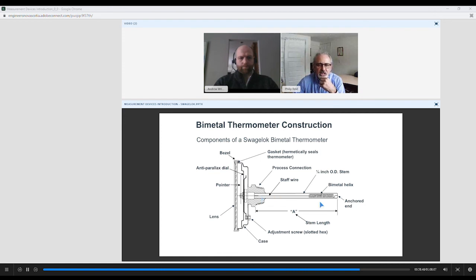You'll have your process connection. You'll have a staff wire inside the stem, and that stem can be up to 72 inches in length or as little as 2 inches in length. So then the bimetal helix is welded to the bottom. And typically you would be threading this stem at the process connection into a thermowell, because this is more susceptible to damage than a thermowell, and I'll explain what a thermowell is in just a couple of minutes.